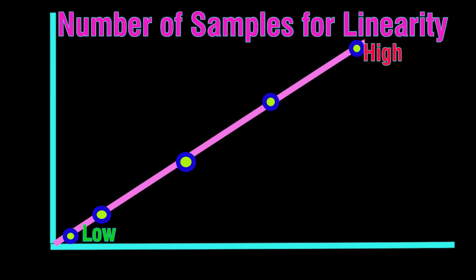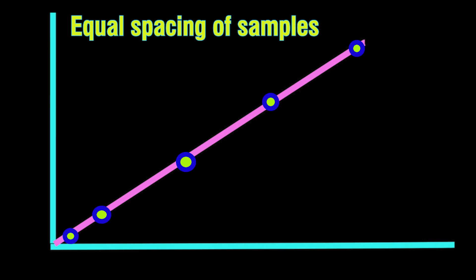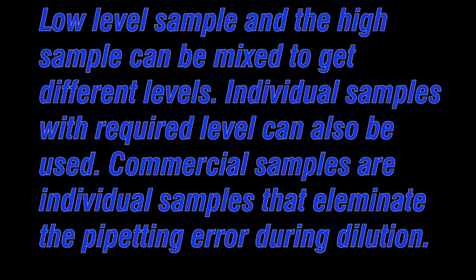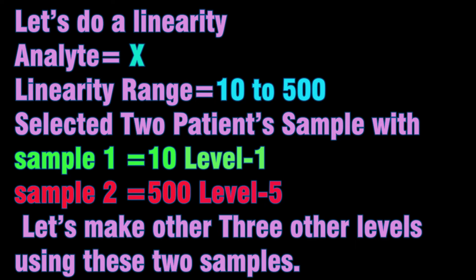How many samples are needed to cover the analytical measurable range? Appropriate evaluation of linearity requires five different concentrations spanning the analytical range. Samples should be spaced where analytically relevant; frequently equal spacing is sufficient. Spiking a biological material with a known amount of analyte, making serial dilutions, or creating mixtures with different ratios of high and low standards are all acceptable approaches to prepare test samples. At least two replicate samples should be run to allow for estimation of random error.